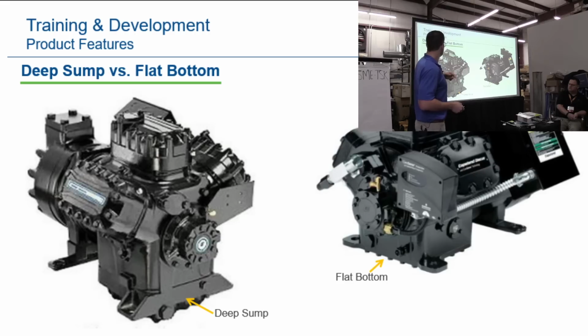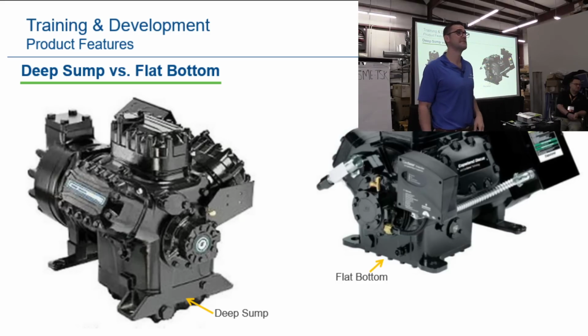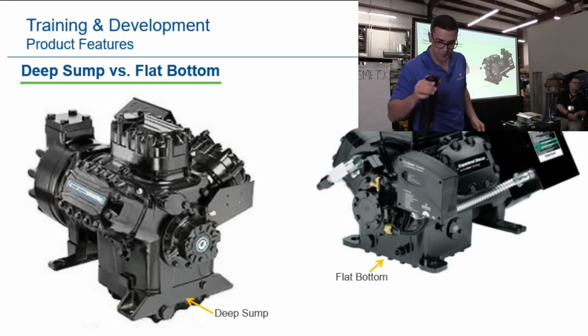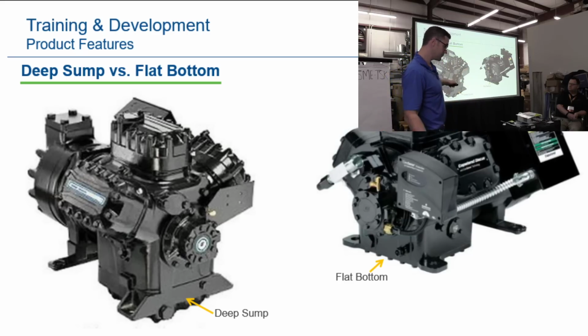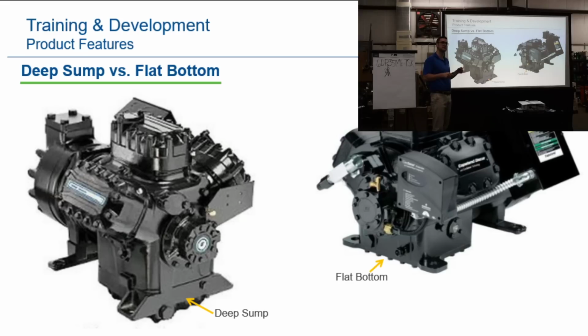Deep sump and flat bottoms. So we have different models. You want to make sure, once again, you have the right model number. Because if all of a sudden you give them the wrong model number and you get a deep sump, potentially it's not going to fit into where it's supposed to. Yes? Are the reed and the Discus different in the short block also, or just from the heads up? Well, right here, as you can see, what was the question again? Are the reed and the Discus the same from the head down?